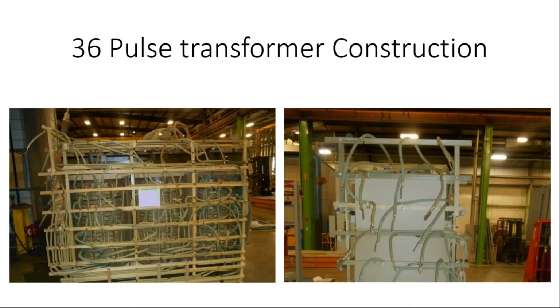We want to share a few pictures of such transformers. Now, this one you see is a 36 pulse transformer, and 36 pulse means it will have 6 LV windings. So each LV winding is rated for 1/6 of the kVA of the HV winding. On the left picture, you see multiple crisscross connections which are made. These are actually making an extended delta configuration of 6 windings. So the 6 windings will have different parts, the extended portion of the delta and the delta.